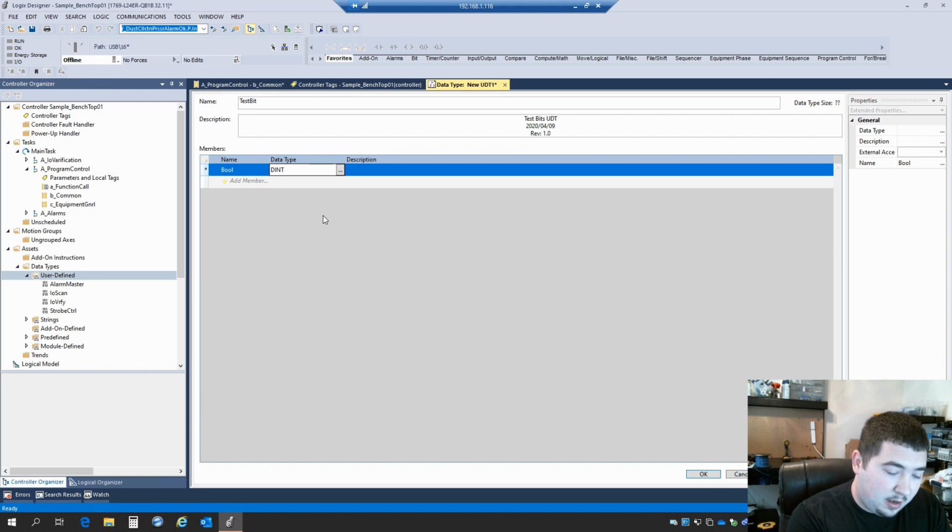So one thing you can do is create an array. And all an array is just saying that I want this DINT, but I want it, let's say, 4 times. So in order to make an array out of a tag, you do an open bracket and then the number of tags or data types you want associated with this.